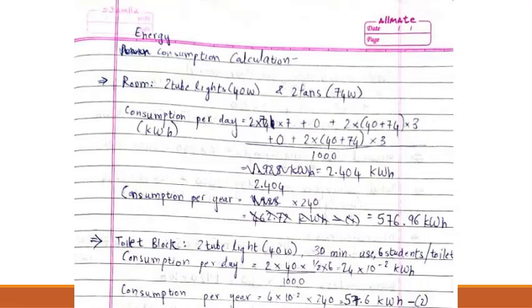For the toilet block, we assume that each student spends 30 minutes per day in the toilet. Since we have two toilet blocks in one wing and 12 students per wing, we effectively have 6 students per toilet. So the consumption per day is given by the following expression, and multiplying it by the number of days per year, we have 57.6 kilowatt hours for the toilet block.